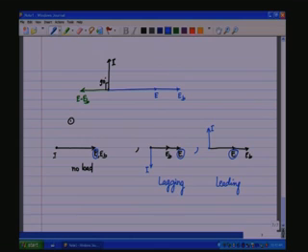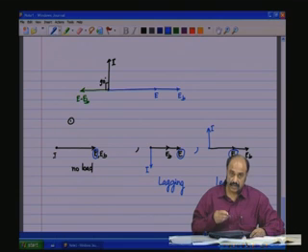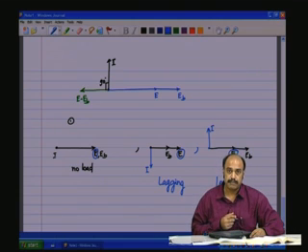This means that we can adjust the power factor of the machine by adjusting EB or by adjusting the field excitation IF. Okay, so this is a very powerful feature which makes the synchronous motor compensate for the lagging power factors of other loads. And that is why the synchronous motor is also called a synchronous capacitor.